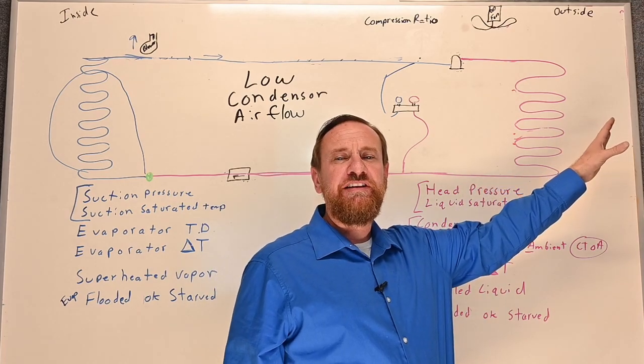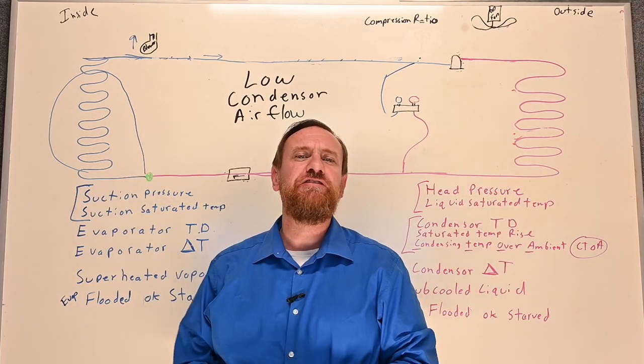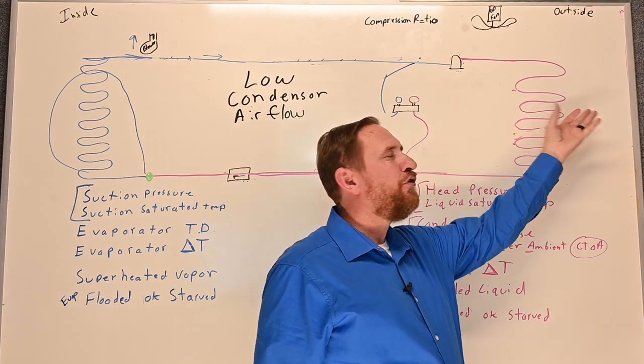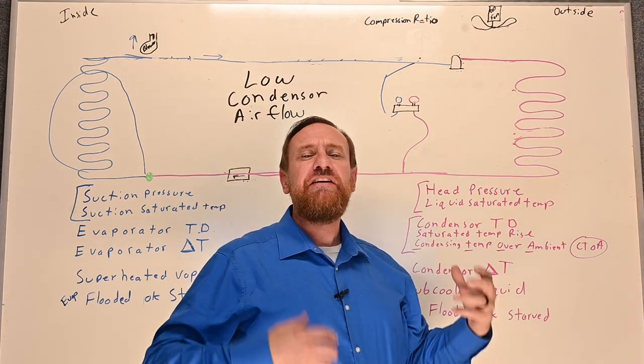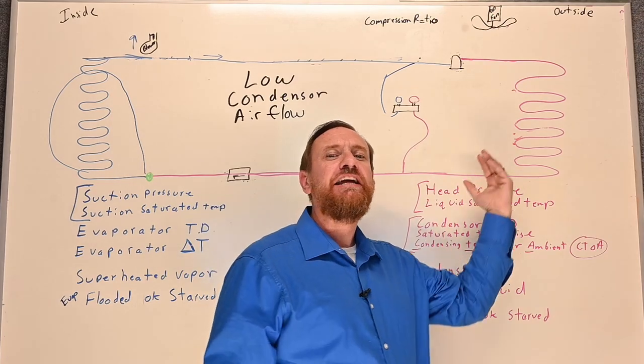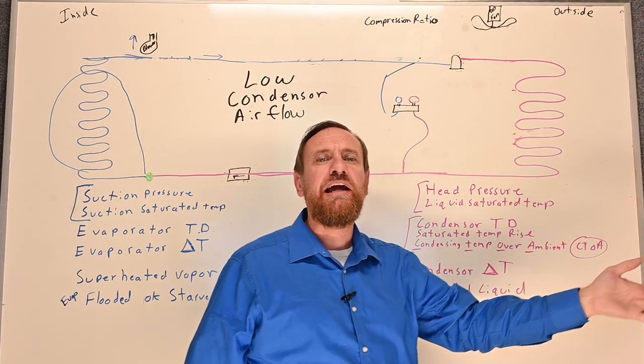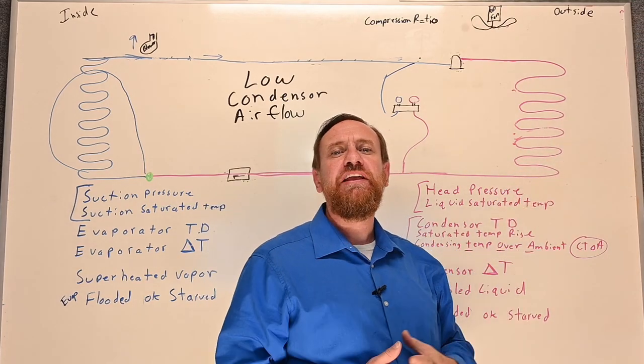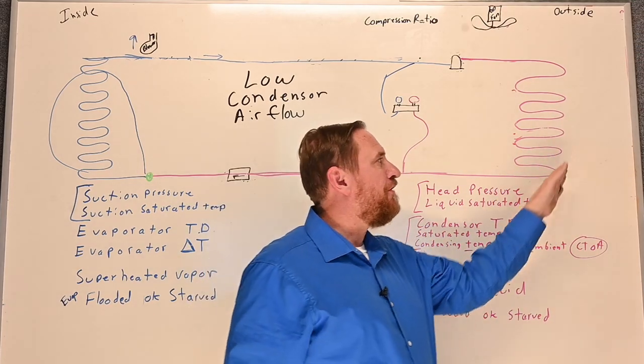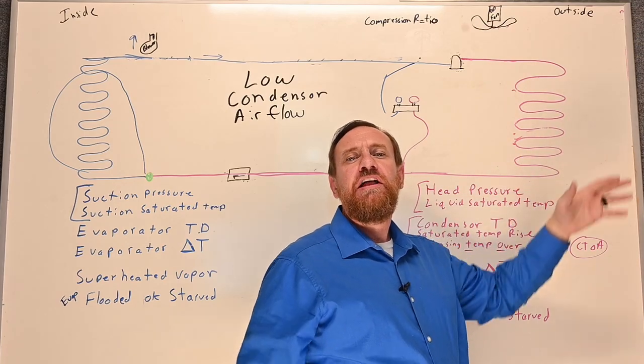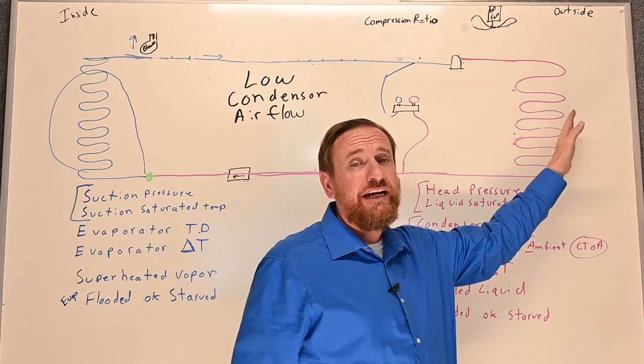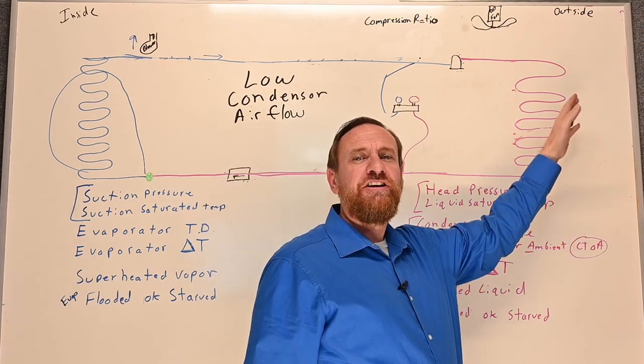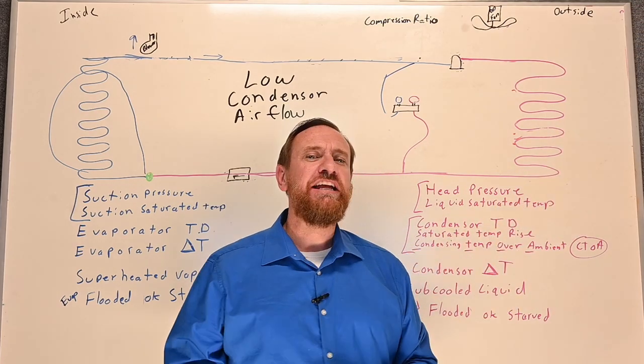If we have blocked airflow in our condenser, it's going to be the opposite of blocked airflow inside. With blocked airflow outside, we have to think that the air is cooling the refrigerant — we're transferring heat from the refrigerant to the cooler air. A dirty condensing coil would do two things: it's blocking airflow, but it's also slowing down heat transfer because that dirt acts like an insulator.